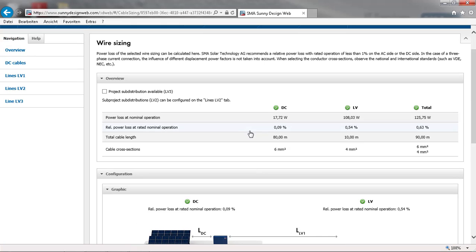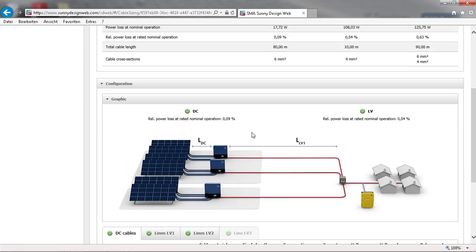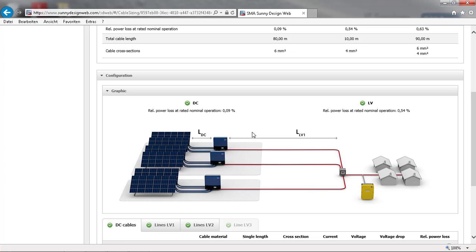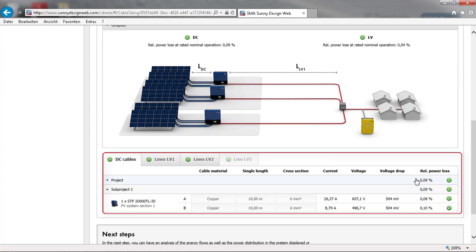This nice feature of Sunny Design allows you to calculate power losses in the wiring. The total power losses should be less than 1%. If this is not the case, you should increase the cross-section of the cable.